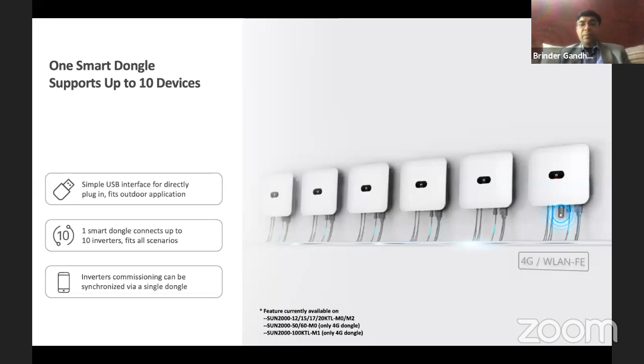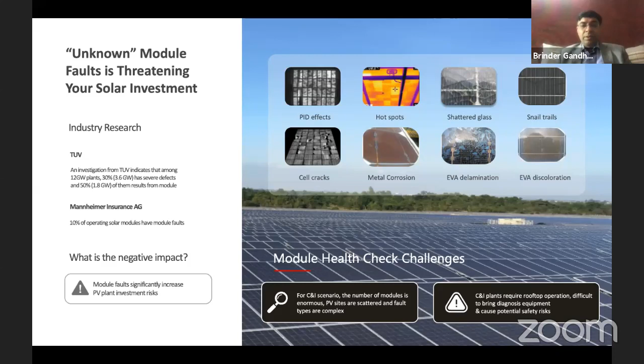We are also focusing on the module faults. So we have brought in a solution in collaboration with TUV, and there are around 14 types of faults which can occur on the modules. With this solution, you can check all the faults. This is our solution where you can run the IV curve for the whole plant without dismantling any module, and you get a complete result for each and every string within almost 10 minutes for a megawatt level plant, which can accurately identify 14 types of module issues with an accuracy of 99.5%.